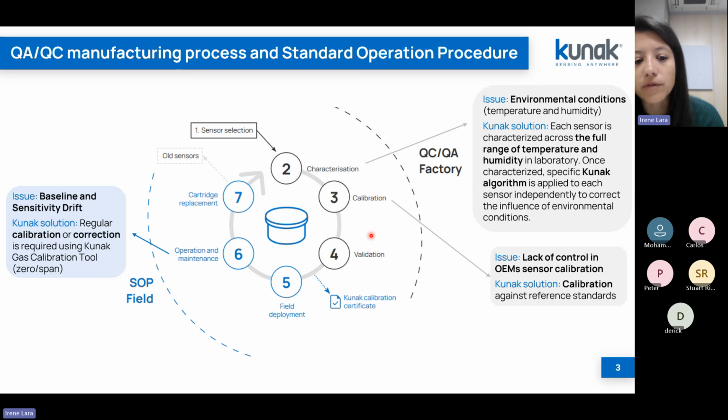So, for example, if we just move from my office to outside and we turn off and on, probably in a few minutes it will be ready. But if the device, for example, comes from Europe to Australia and you have to turn it on, maybe you will need some days. We recommend between 2 days and 1 week for stabilization.